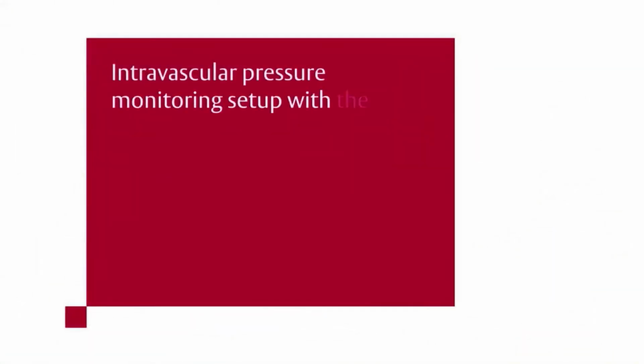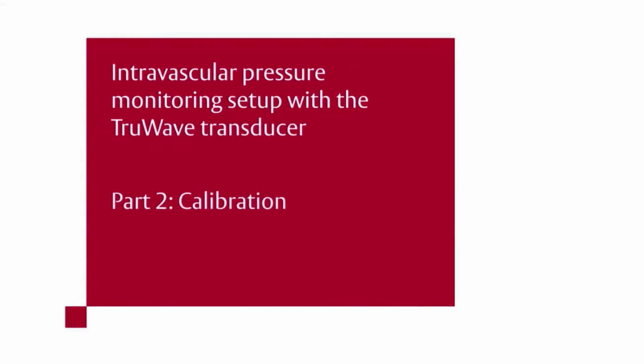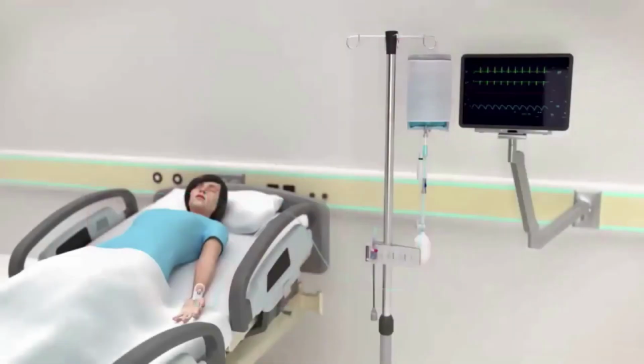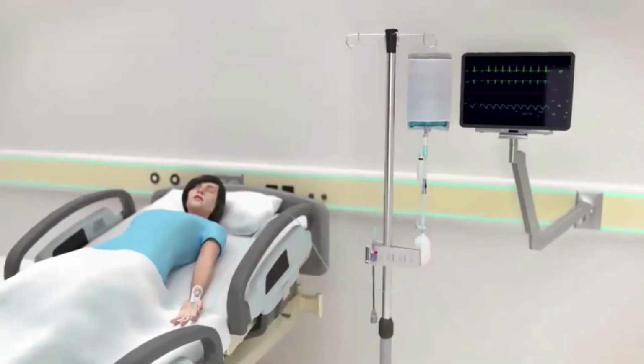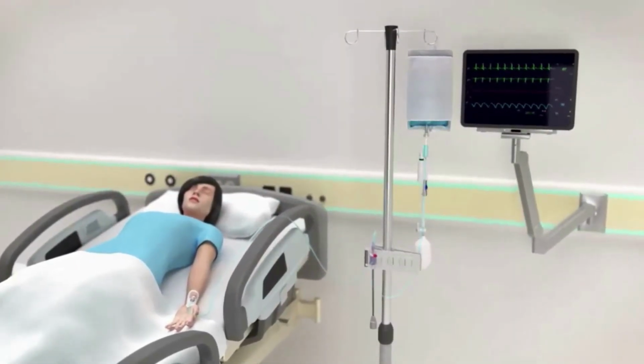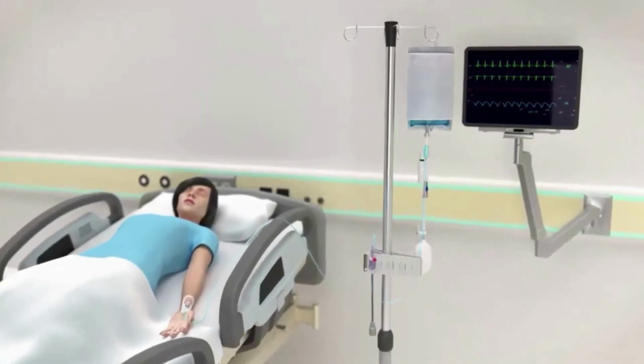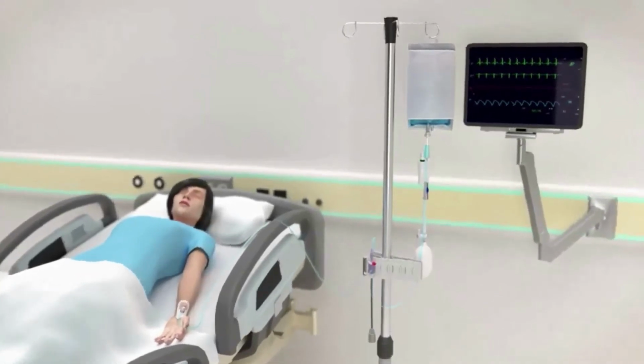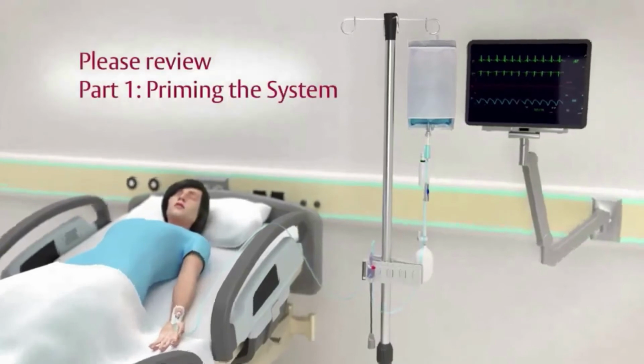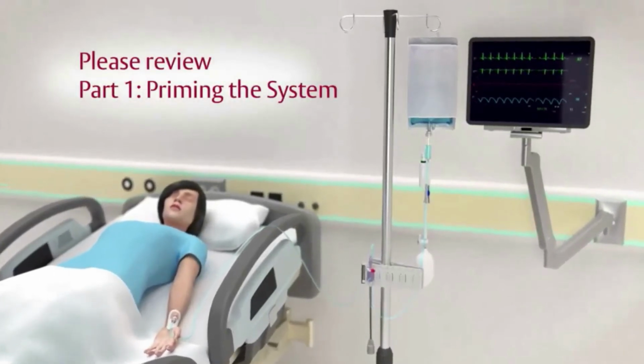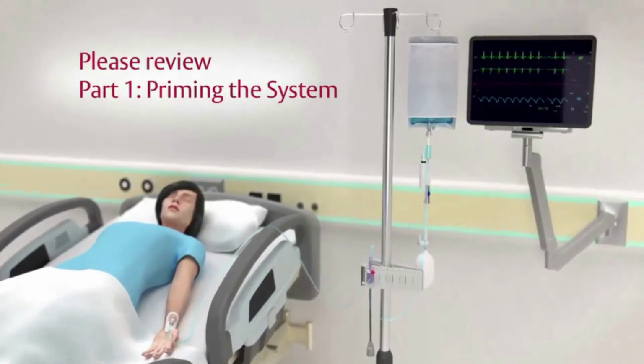Intravascular pressure monitoring setup with the TrueWave transducer. Part 2, Calibration. Before connecting the TrueWave transducer to a bedside monitor and calibrating the system, it's important to prime the system properly. If you haven't already done so, please follow the steps in Part 1 of this video series, Priming the System, to complete this procedure.